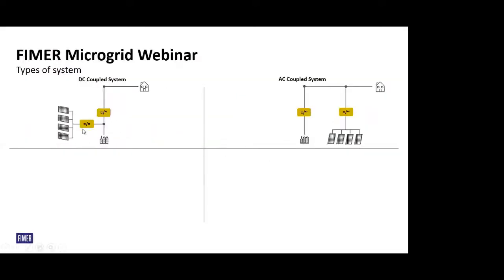Here, if you go back, only one converter charges the batteries, and the efficiency of the MPPT DC-DC converters is usually more than 99%. So most of the energy you generate will go into the batteries here. Whereas it will pass through two converters in order to go to the load. So DC coupled is preferred whenever your intention is to store the majority of the energy you are generating. Whereas AC coupled works out well where you want to store only part of the energy and send the majority to the grid. Let's say utility scale solar plants, where you want to store the energy for your night consumption, usually not more than 2 to 3% of the generation capacity. Then AC coupled is best, because whatever you generate is going to loads, and only 2 or 3% is charging your batteries.